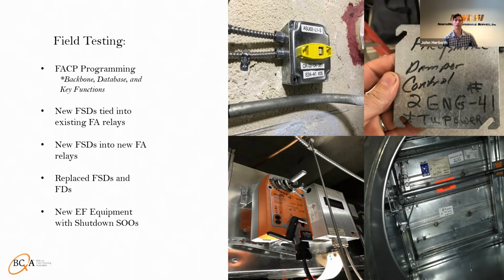And so there are going to be some wiring issues that you're going to run into, and you're going to need an electrician with you at the time, as well as the fire alarm contractor if it was a programming issue. And then you yourself have to be documenting this entire time and coordinating the effort. So you need a minimum of 3 people there running the scenario, and then also taking a look at the HVAC systems to make sure you haven't impacted any other systems. So it tends to be a 3 to 4 person job at night to work on some of this stuff. And you can't figure it out until you test it.